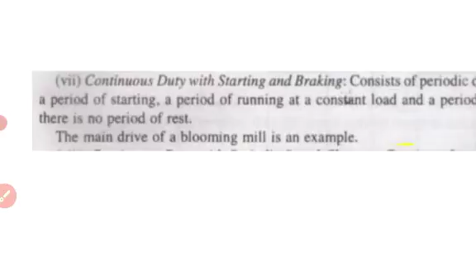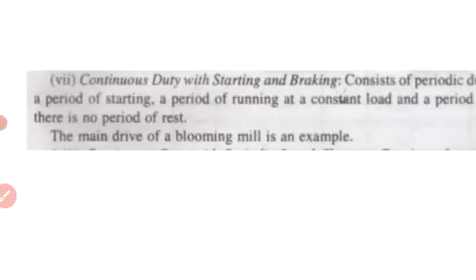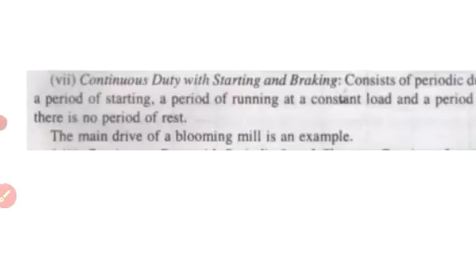Next is the continuous duty with starting and braking. It consists of periodic duty cycles, each having a period of starting, a period of running at a constant load, and a period of electrical braking. There is no period of rest. This is the difference: earlier there was a rest, here there is no rest. Again it will be a cycle, it will be continuous. Hence it is called continuous duty with starting and braking. These are the examples. The main drives of a blooming mill are an example.